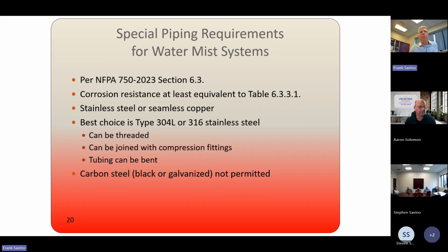So what are some special piping requirements? For that, you have to go look at NFPA 750, section 6.3. You need to have corrosion resistance. They have a table there, 6.3.3.1. So really what it boils down to, there's a lot of different options, but it comes down to stainless steel or seamless copper. We kind of concluded, based on our analysis of costs and everything else, that either 304L or 316 stainless steel was the best option.